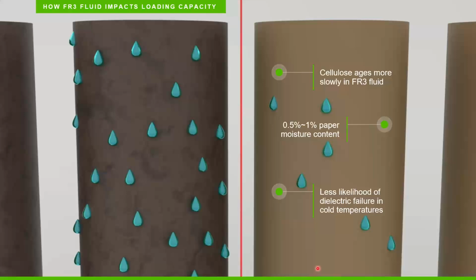And as I said, the second point that makes the degradation of the paper run faster is moisture. A new transformer filled with mineral oil has a moisture content of insulation around 0.5%. After working for a few years, it starts to rise to 2%, and at the end of life, a typical value is above 3%. This is because water is a byproduct of the degradation of the paper. So the paper degrades, it generates water, but this water also accelerates the degradation process. So we are in a circle of degradation. It's what we call a self-induced reaction.